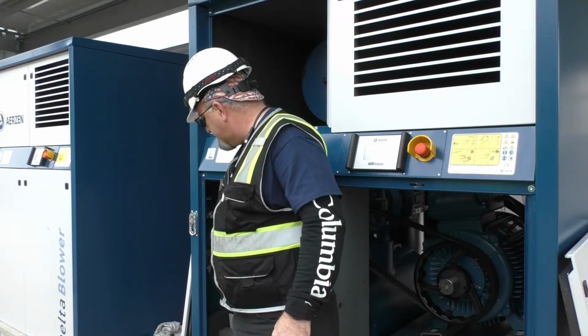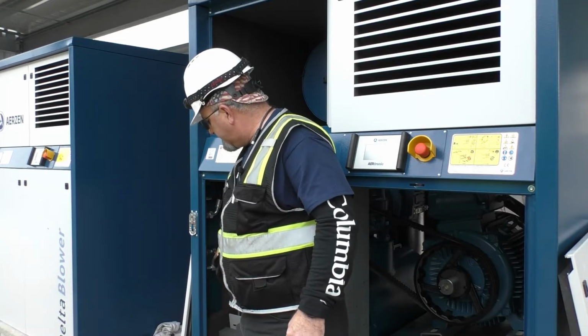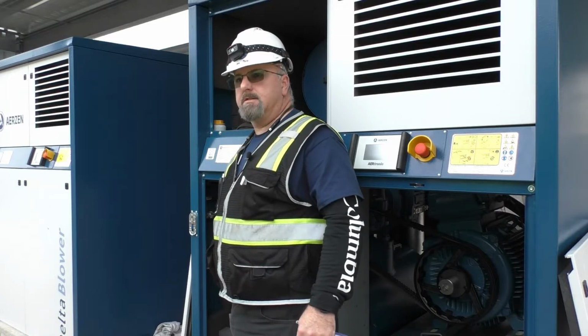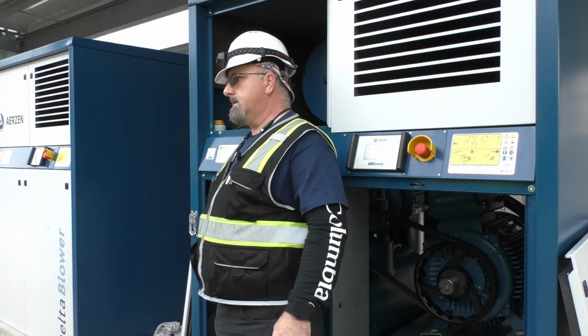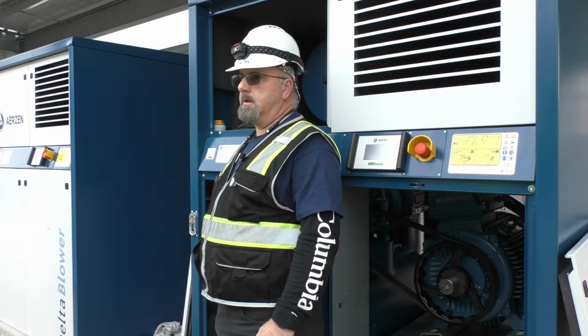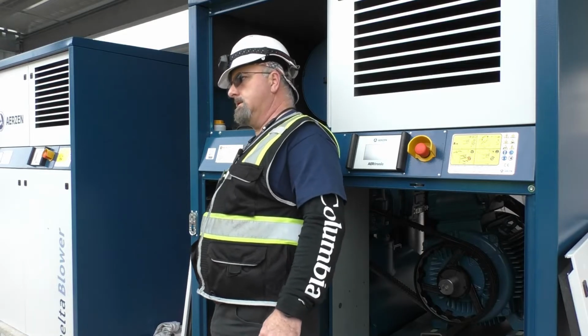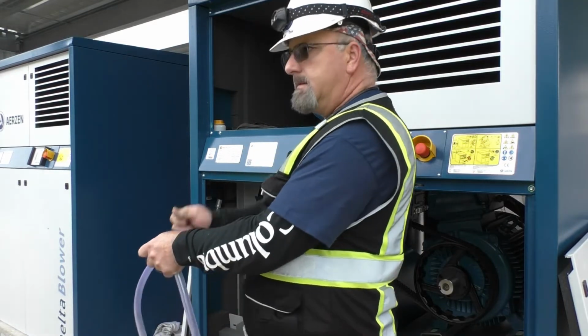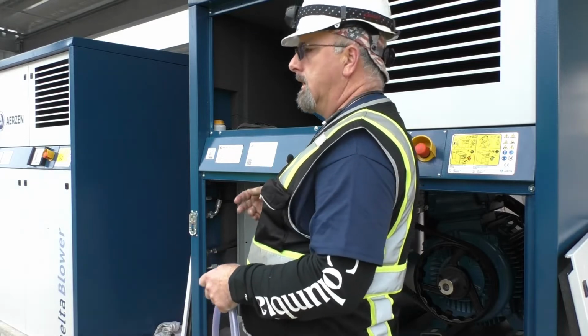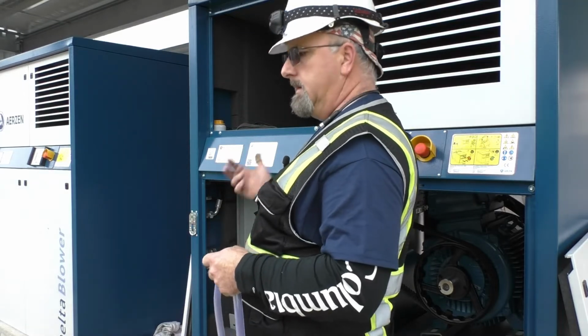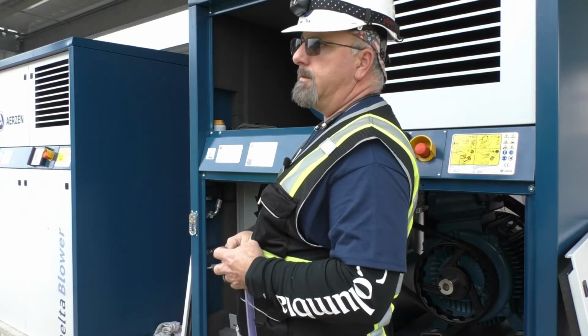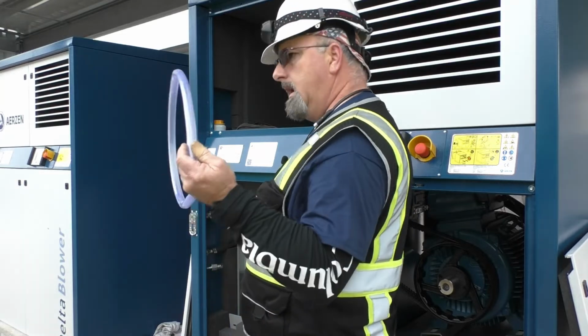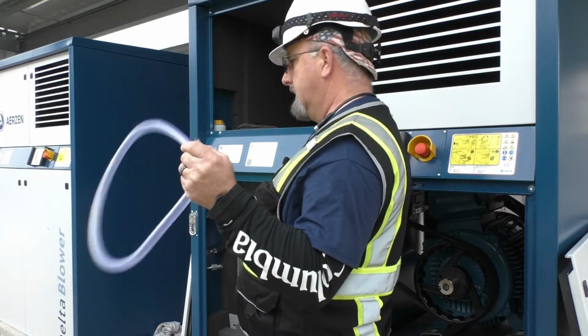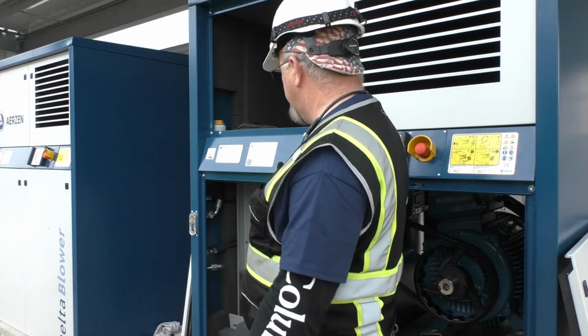Now, one thing I will say is where this piece that it screws into is attached to this tube, do not spin that on that tube. It will cause it to start leaking and you'll have to replace that whole section of tube. So take 2 wrenches, break it loose, take it out. You can try to clean it. If it doesn't stop leaking, then you'll have to replace it. Any questions on draining oil? I mean, it's pretty straightforward.